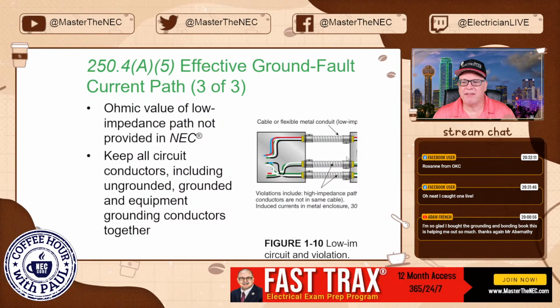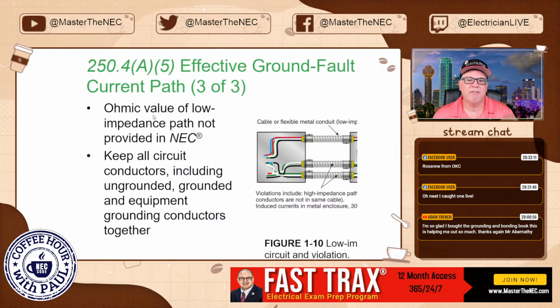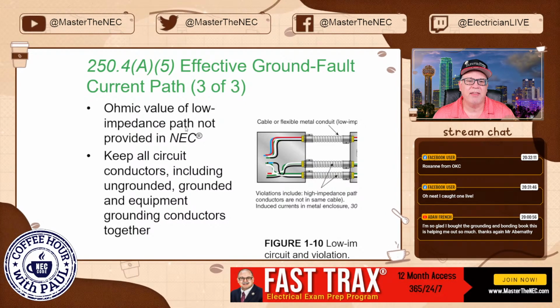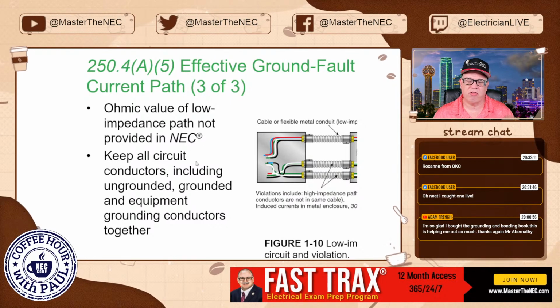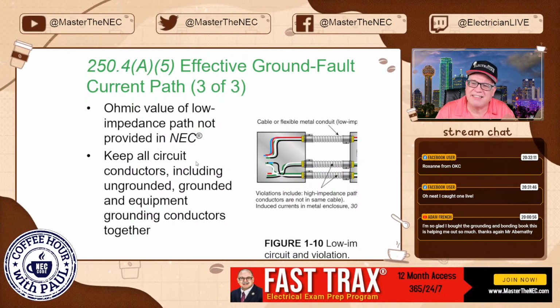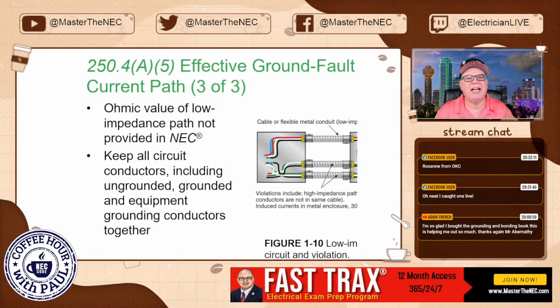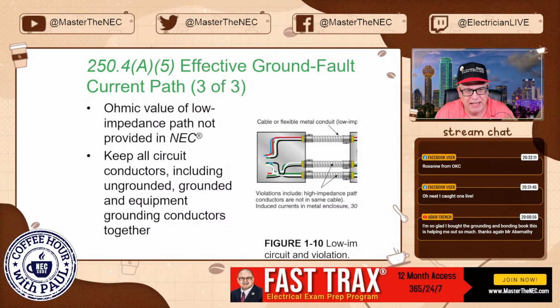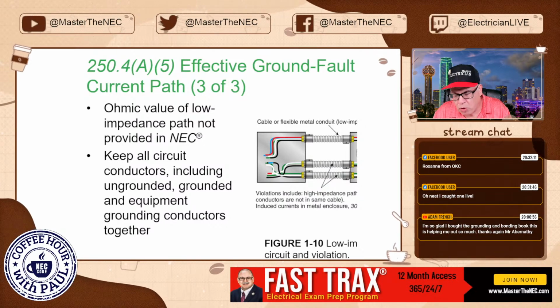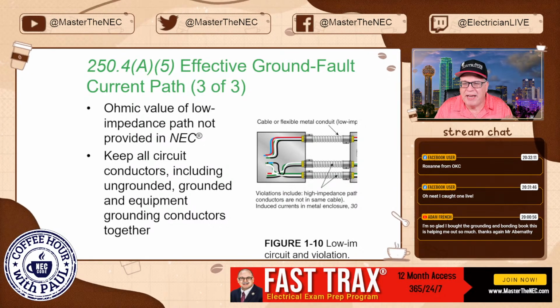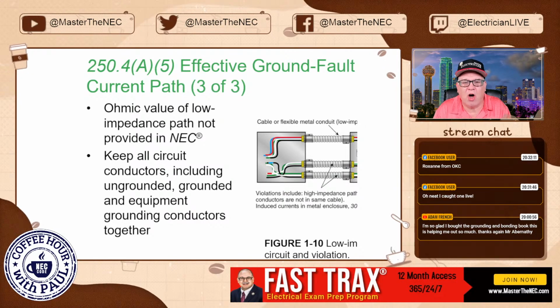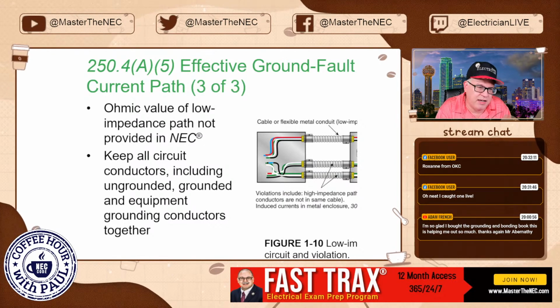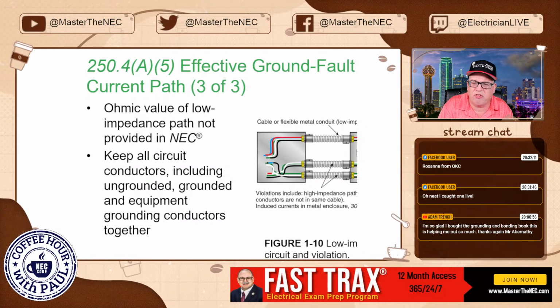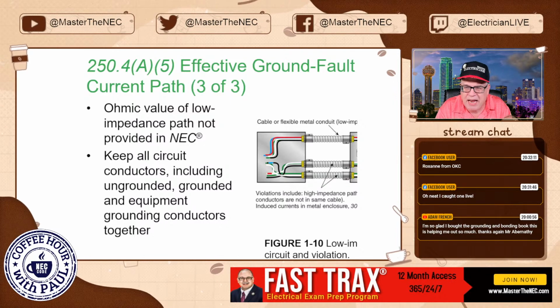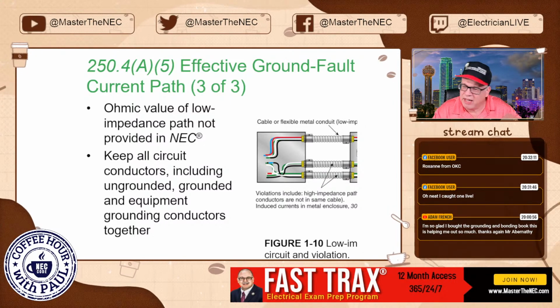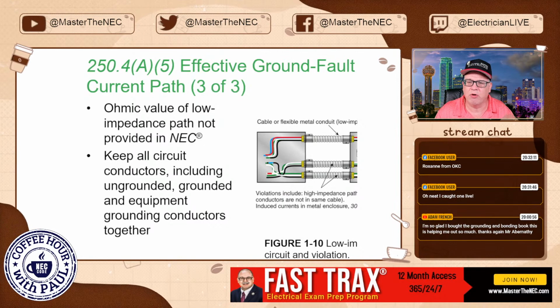Effective ground fault current path. Let's look at some examples here. The ohmic value of a low impedance path is not provided in the NEC. So it doesn't necessarily tell you what constitutes a low impedance path. It just gives you the prescriptive requirements to best achieve it using all of the electrical components, fittings, couplings, lock nuts, proper cable or raceway. It assumes you do everything together in order to do this.